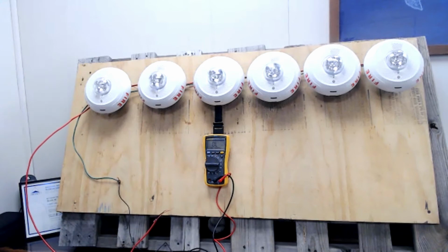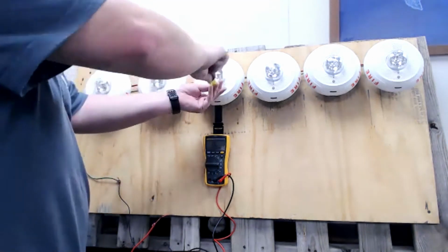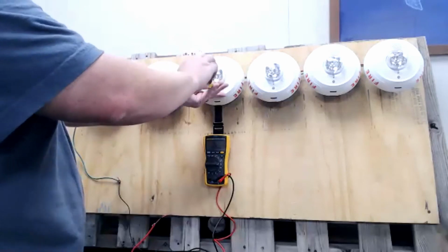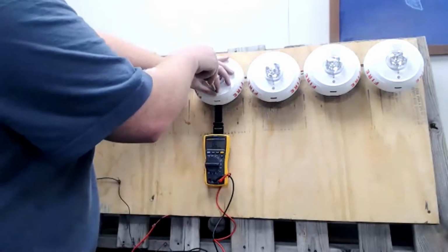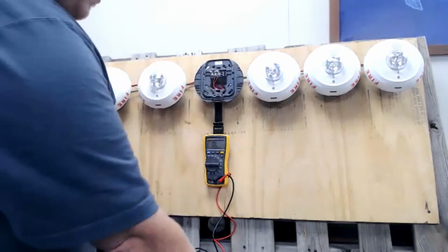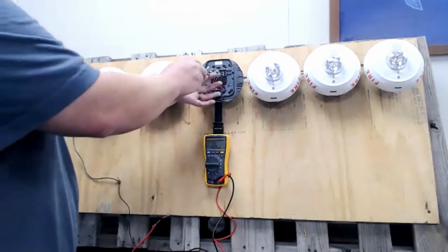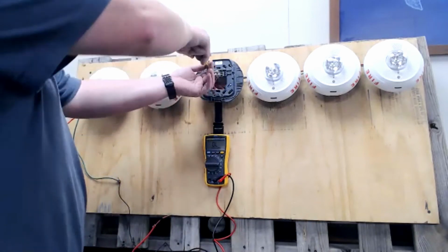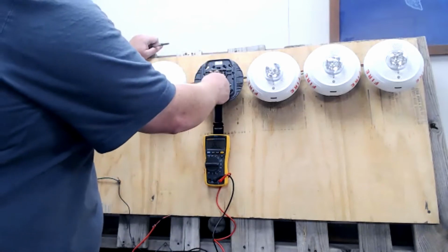But to chase it, we're going to chase it very similarly to how we just chased the open circuit. We're going to come right here, and go back to our center device. The thing is, I'm really failing at this right now. All right, open that back up. And so we know it's not on our positive side, it's on our negative side. So I'm only going to remove the negative wire. I don't need to chase the ground fault on the positive side because it's not there.